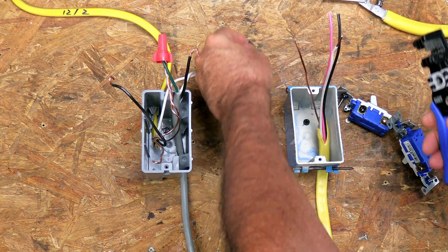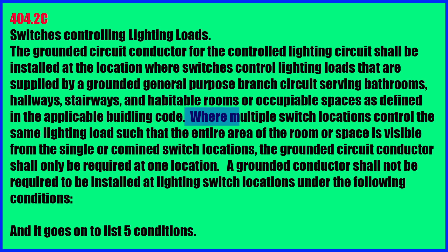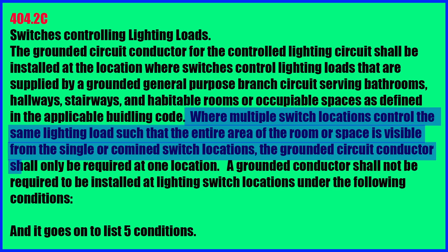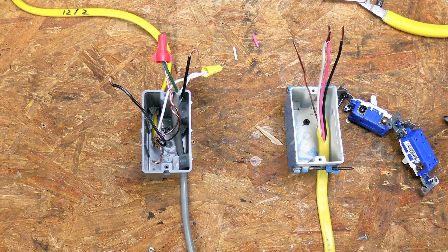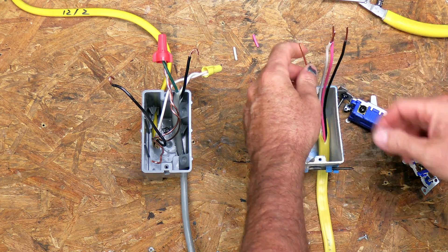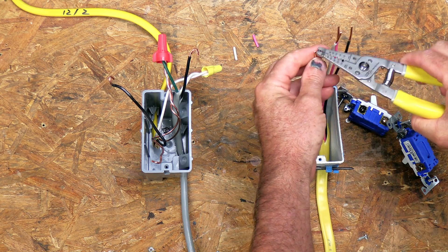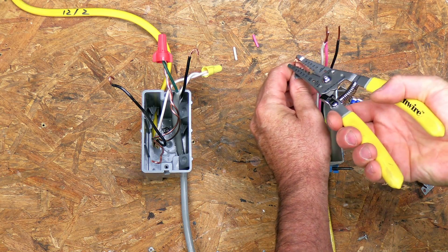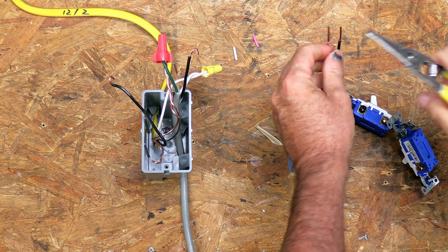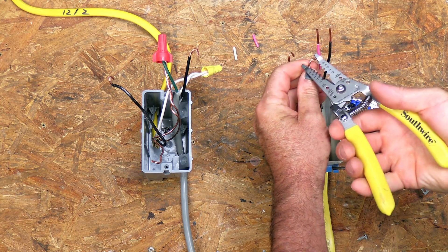Now you might be thinking, there is a code that says you have to have a neutral at every switch location or at most switch locations. But in this case, as long as you can see the switch, like if you can see the second switch from the first switch, both switches are visible, actually code 404.2C, I believe it is, you don't need a neutral in the secondary location as long as the primary location has the neutral, so keep that in mind as well.